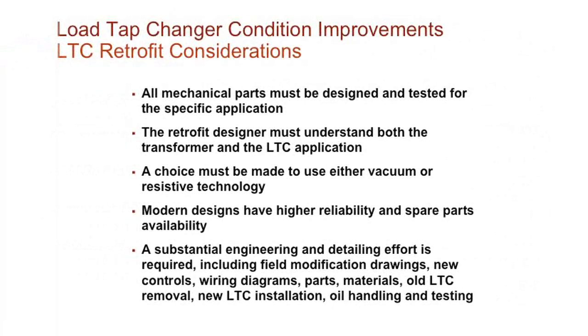Basically, all the mechanical parts are designed depending on the application. We talked about that. We use a retrofit engineer, so he understands both the transformer and the LTC. And I think that's a critical point. We know there's some replacements going on where the transformer design is not being looked at. They're just looking at one for one, trying to match up an LTC to what the existing LTC is. And you can run into a lot of issues there. It's just like changing something out on your car. If you don't know exactly what you're replacing it with, you can run into a lot of problems. Same thing and even more extreme on an LTC, because you can have a failure depending on your voltage levels and your current levels in your LTC.